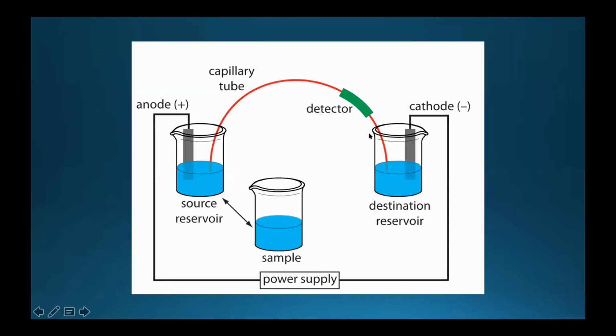So this is the schematic of the system. There are many different types of capillary electrophoresis, and they have some changes within this, but they all generally operate under this system. There is a power supply that puts a high voltage, up to 30 kilovolts, into the system. That voltage is carried through to the electrodes at both sides, which carry the power throughout the whole system.